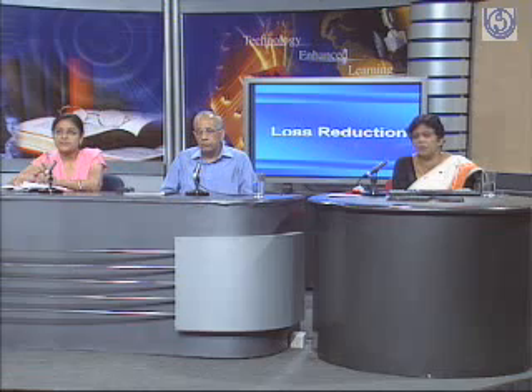The maximum amount of power which one can transmit over an 11 kV feeder will depend, first, upon the size of the conductor, and second, the power factor of the load. For different conductors we can carry different amounts of power because the current carrying capacity is different. You will have to calculate the current carrying capacity, and from that work out the power that can be carried over an 11 kV feeder. It can vary from say 2 megawatt to about 5 megawatt, depending on the current carrying capacity.